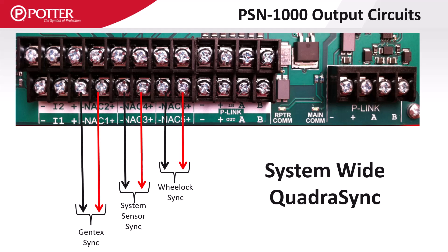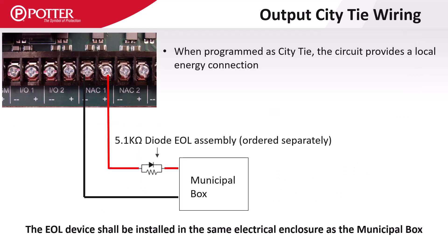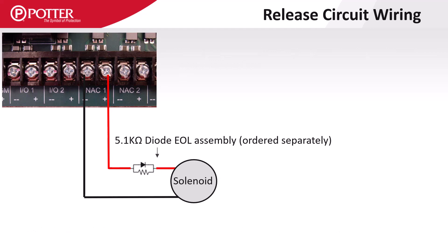QuadraSync is supported on PSN1000 Intelligent Power Supplies, allowing four different strobe sync protocols to be used on separate circuits. The P-Link connection at the power supply provides master synchronization across the entire fire alarm system. Both NAC and IO circuits can be configured for municipal box service or releasing applications. Both options require an end-of-line diode resistor assembly, which is sold separately.